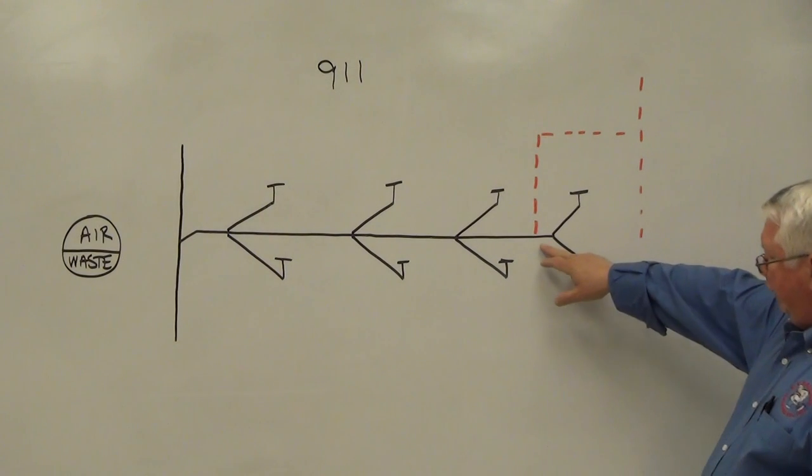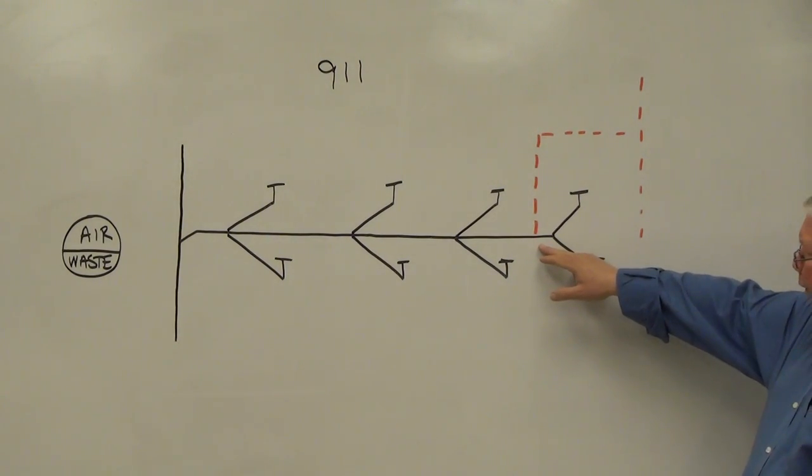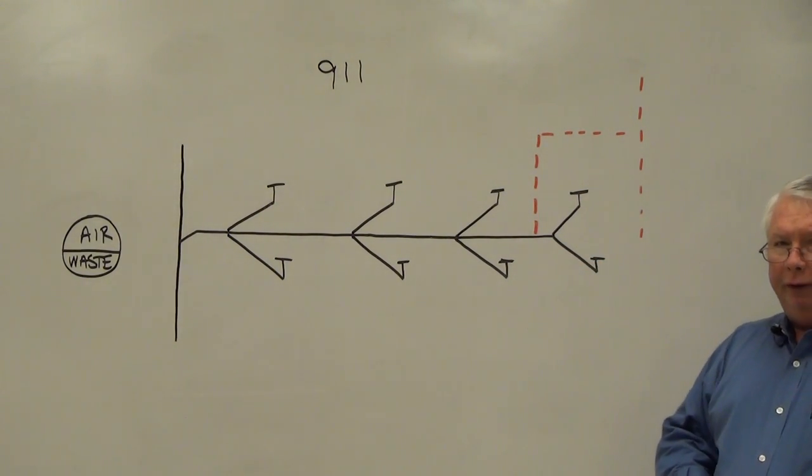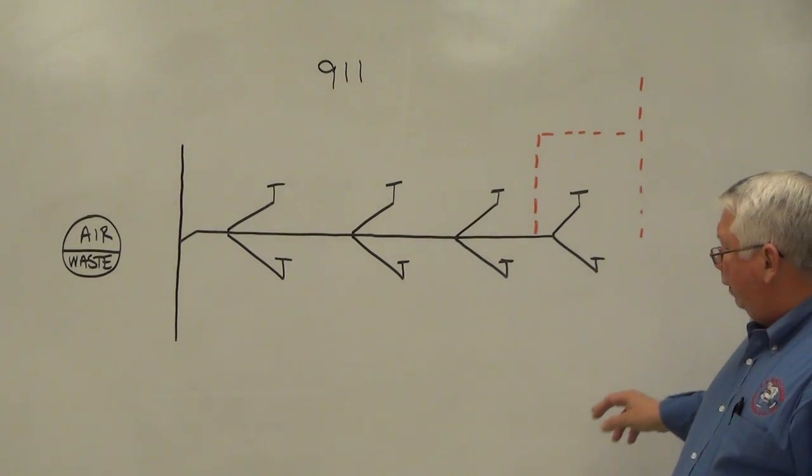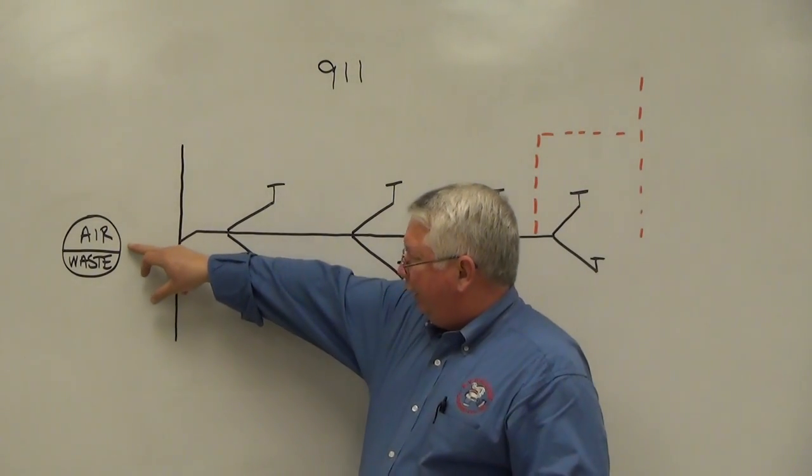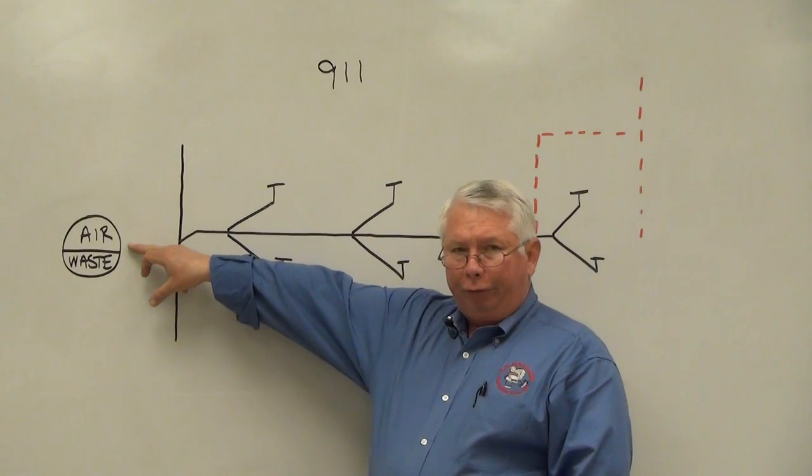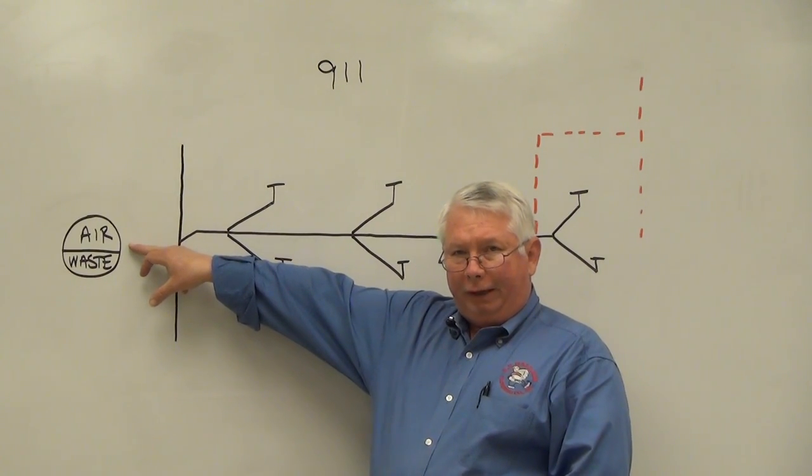The circuit vent pipe connects between the two most upstream fixture drains and it connects on the top of the pipe, therefore allowing the vent connection to be where the air is traveling through the horizontal branch drain that's being circuit vented.